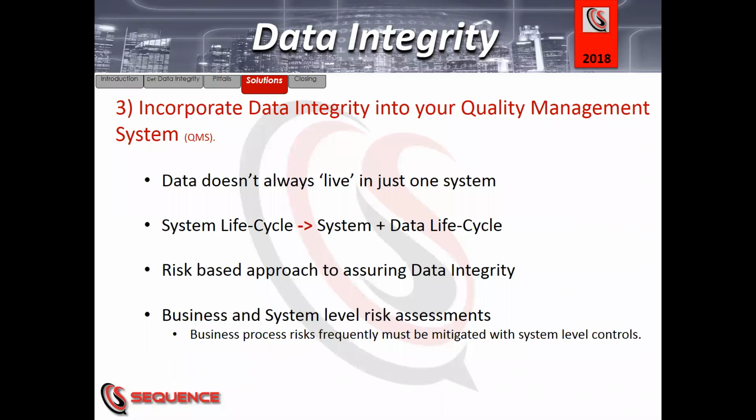But how are they going to know what data is critical, and how are they going to ensure they have the appropriate data integrity controls, and how are they going to ensure that they have consistent data integrity controls with a data integrity program, so you can maintain a modular consistency in ensuring data integrity throughout your operation? So the answer to that would be, if you have an overall strategy, a business level risk assessment or business level strategy, that will give them something to look at and understand how their technical piece fits into the parent process flow.